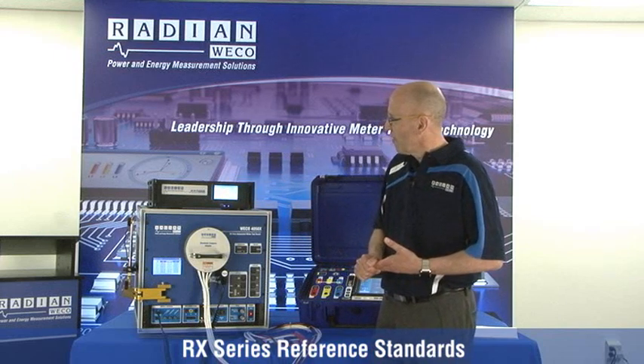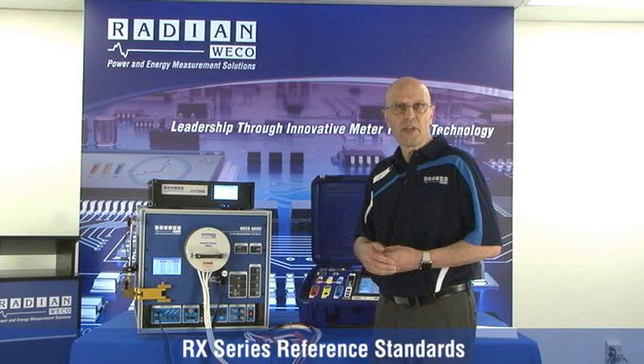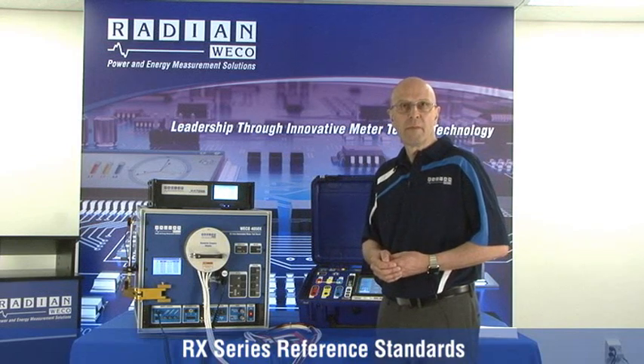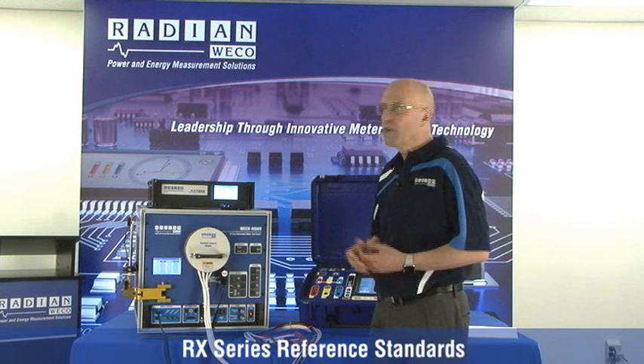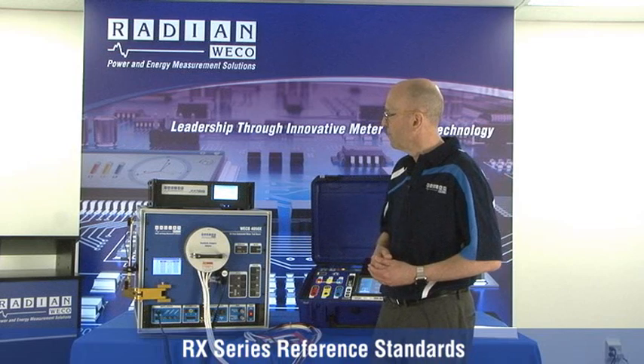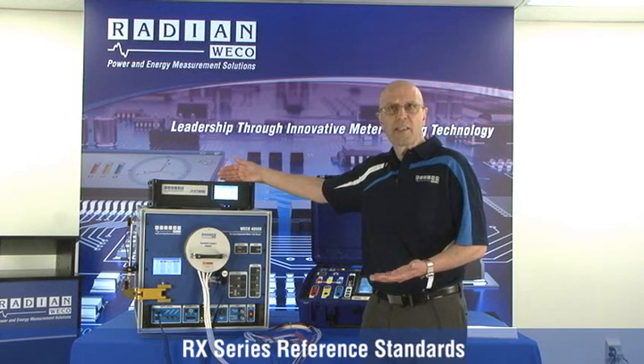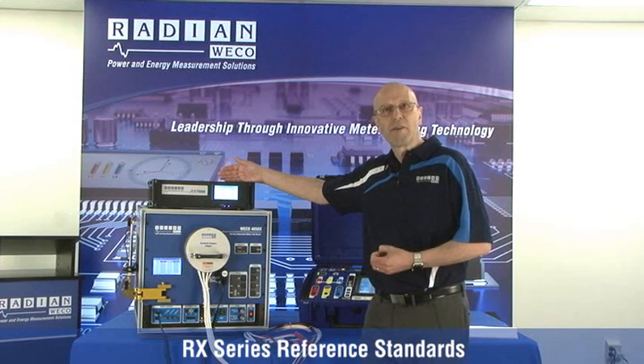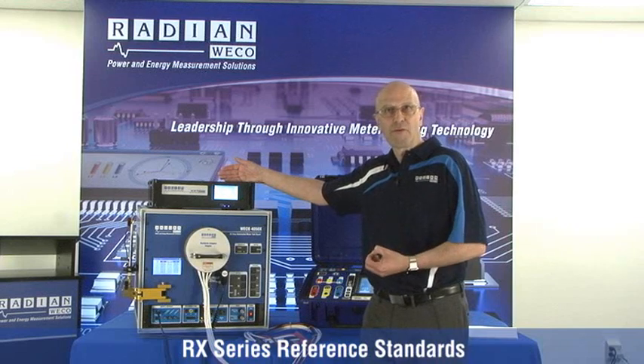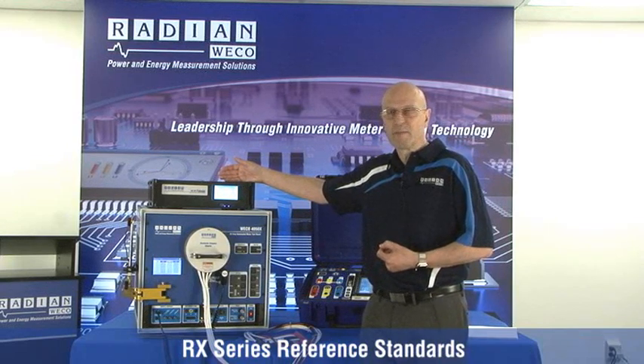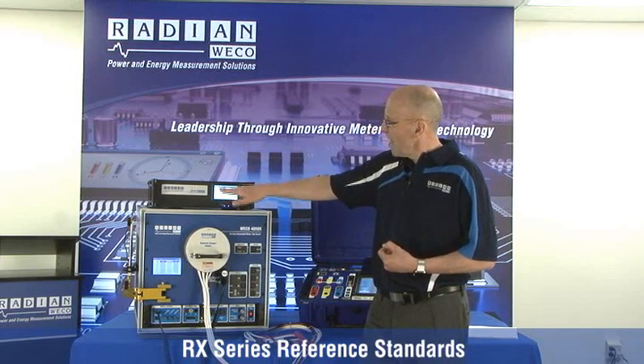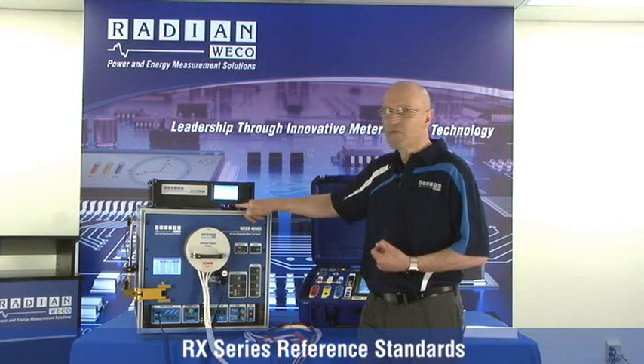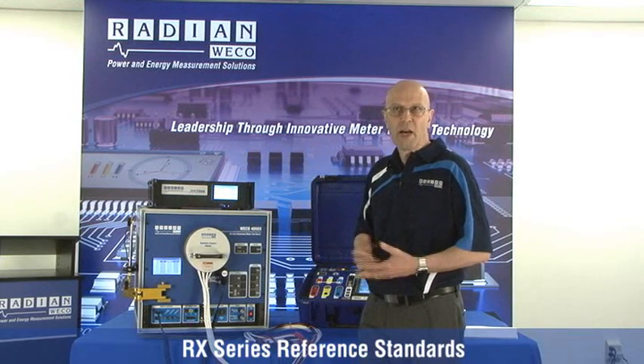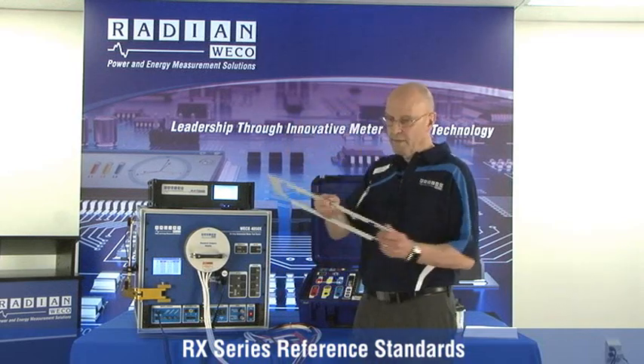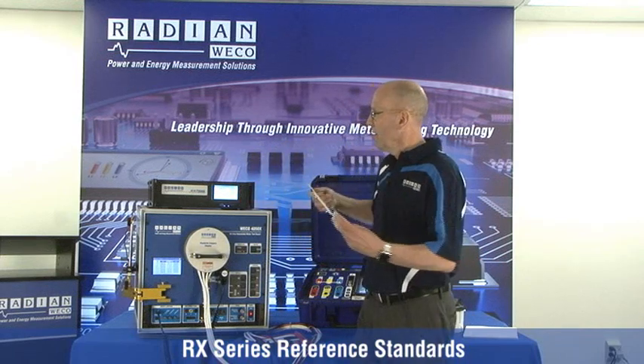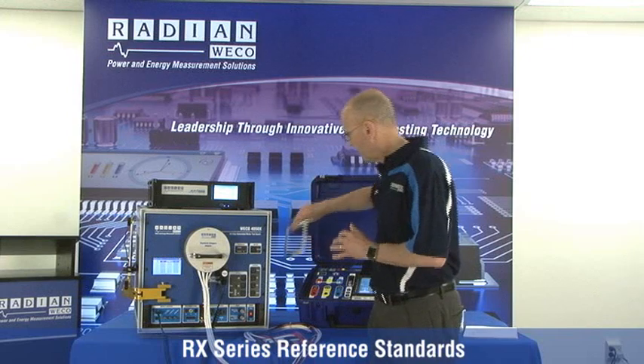On the display of the RX reference standard, you see we're able to measure active energy, apparent power, as well as reactive energy, as well as phase angle and frequency. We also display the RMS voltage and current of every channel. The RX3 series is a three-phase device. We also have the RX2 series, so 2X, 2.0, 2.1, and 2.3, similar class accuracies, to accommodate single-phase measurements. The display here is bypassed if you wish to connect an external touchscreen monitor to increase the size of the display for other applications. This benchtop configuration with the rack mount option can be changed to accommodate a system application.